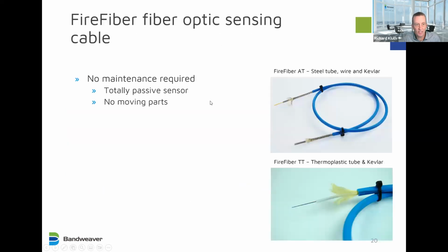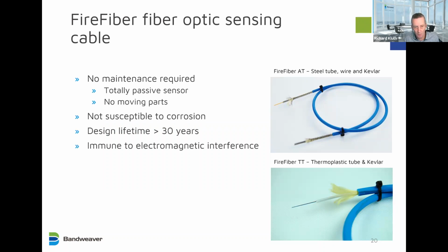The sensing cable, as we said, is standard, based on standard telecoms grade fiber optics. So it's totally passive, no moving parts and no maintenance required. These things are not susceptible to corrosion. They can last much longer than 30 years. Some cables have been in place for more than 50 years. It's a very robust cable. It's immune to electromagnetic interference, and you have no in-field power or network requirements, no comms. So it's a very, very simple install.